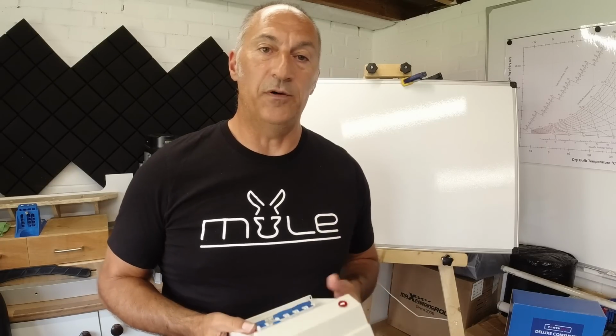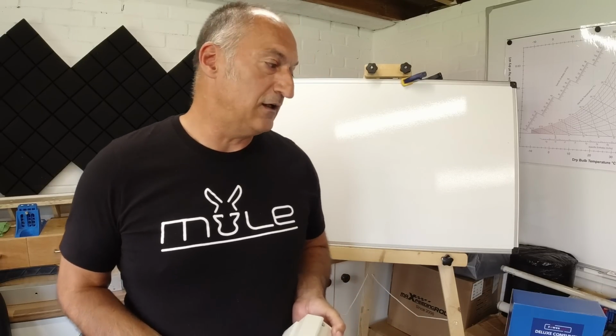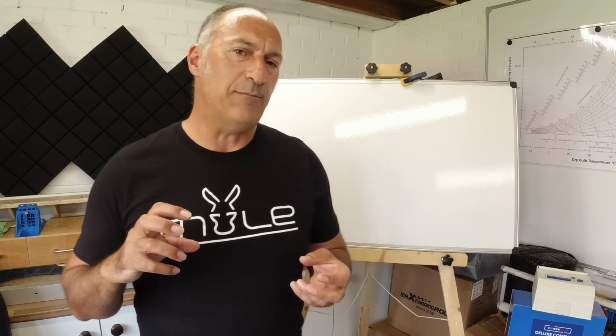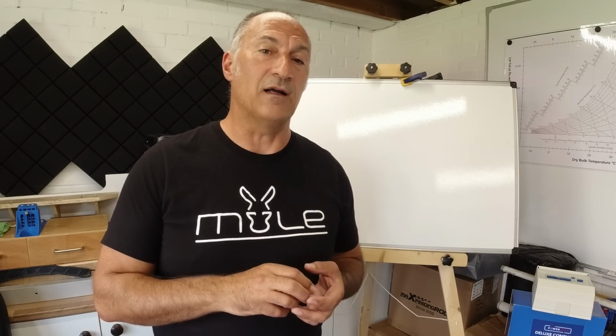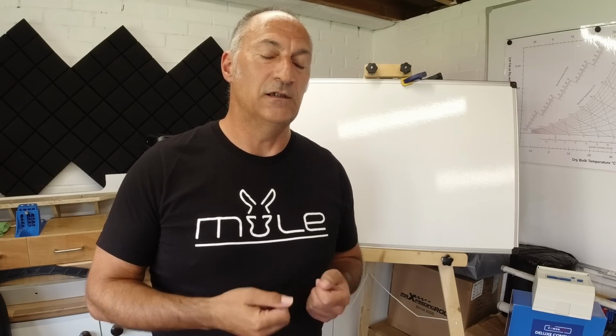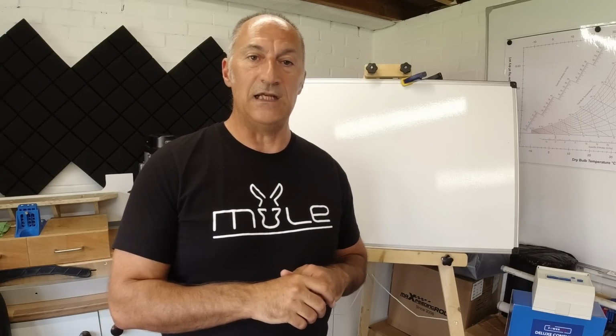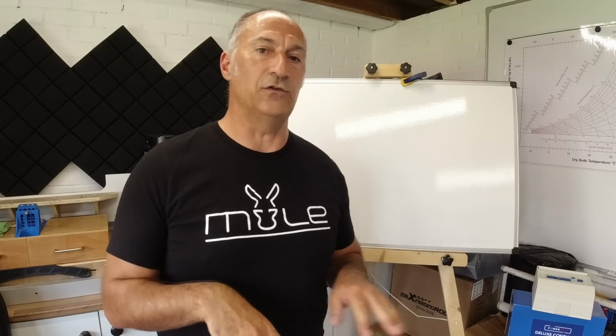I will obviously need to put an overcurrent device, a fuse or a breaker, downstream, but as I'm plugging a 3-pin plug into the output of the inverter, there'll be a fuse inside that 3-pin plug, which will give me overcurrent protection. So I know I'm covered. I won't need an additional consumer unit. But check with the supplier of your inverter, because a lot of them don't have any means of RCD protection built in, and you'll then need to have an additional RCD external to the inverter on that outgoing supply.